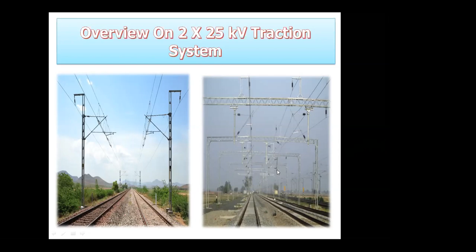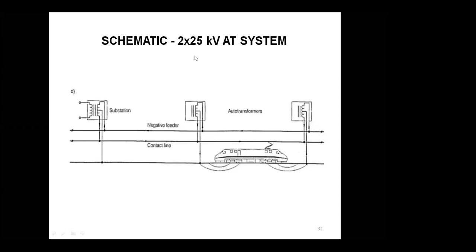A schematic diagram is shown here. We will not go into technical details. This is an auto transformer. One leg is connected to the negative feeder, one rail is connected to the OHE, and the center point is connected to the earth. So the locomotive experiences only 25 kV, but current circulation is of 50 kV. So current in this area will have only limited amplitude, and after that it will be a 50 kV system current. So voltage drops will be less, and any other advantage we are gaining will be available to us. Nowadays in the dedicated freight corridor, this system is also adopted in some places.